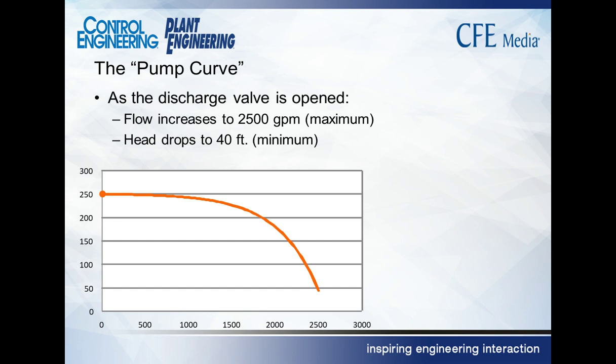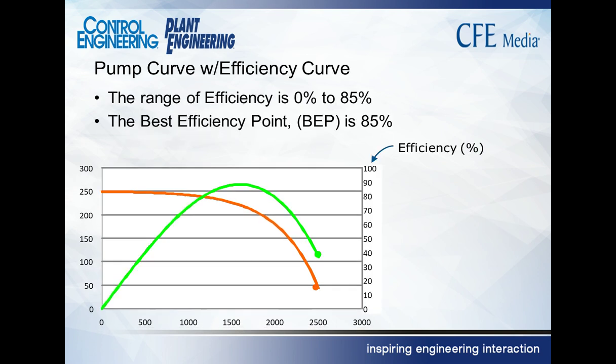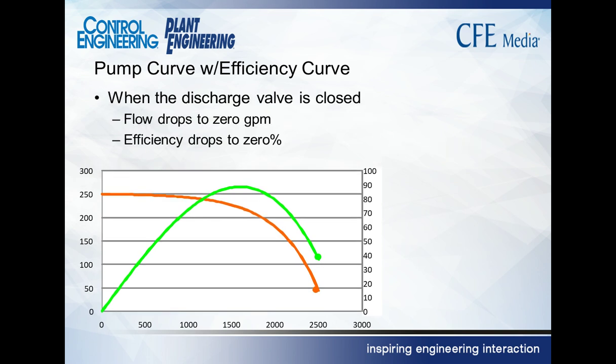Now the efficiency of this pump changes throughout that range of flow. The efficiency, in fact, if I close the discharge valve down completely, it would be zero. But let's just close it down here a little bit. And as I close it down, the efficiency will come up to a best efficiency point. It was 85%, and then as I continue to close it, it'll go all the way down to 0.